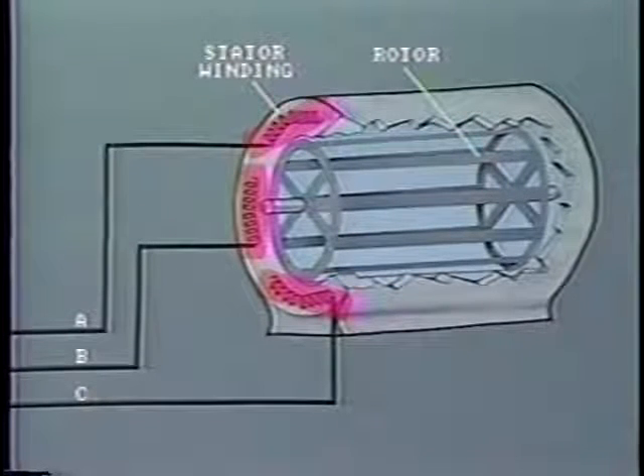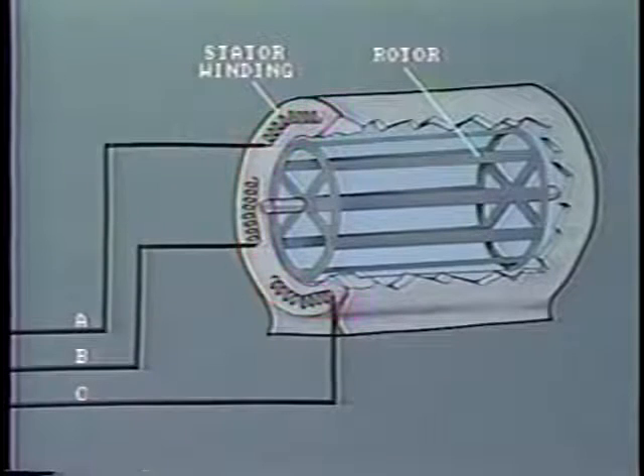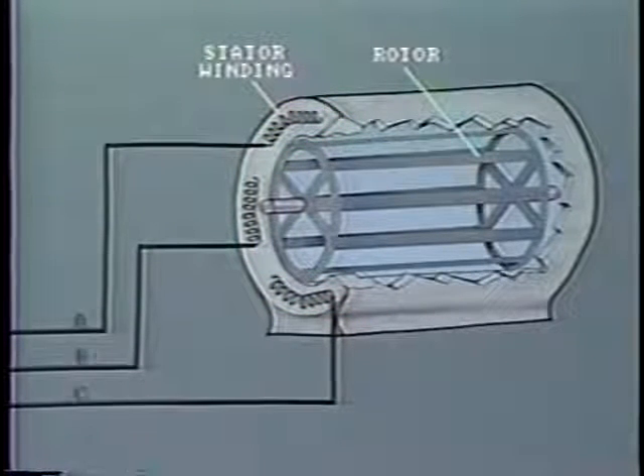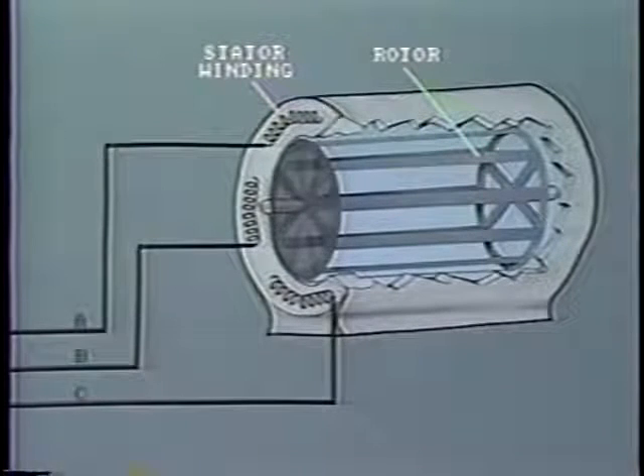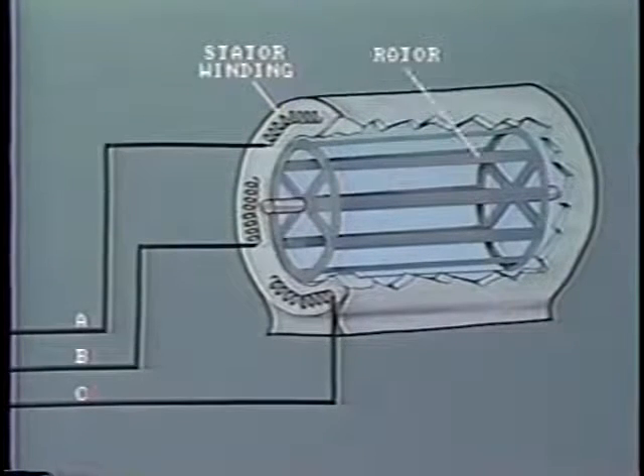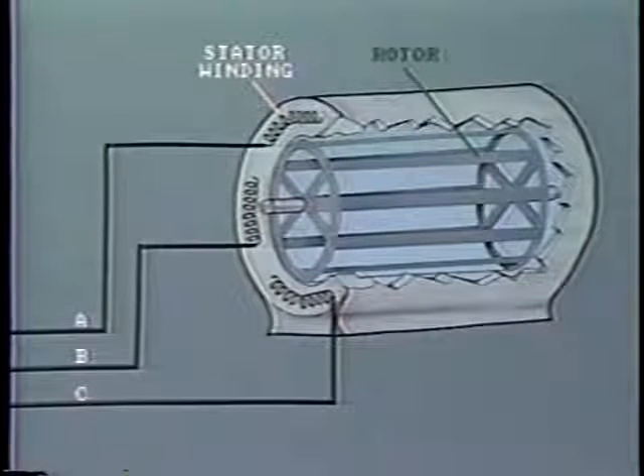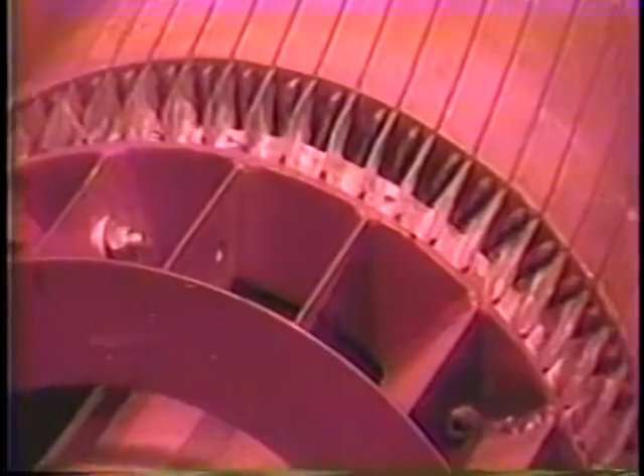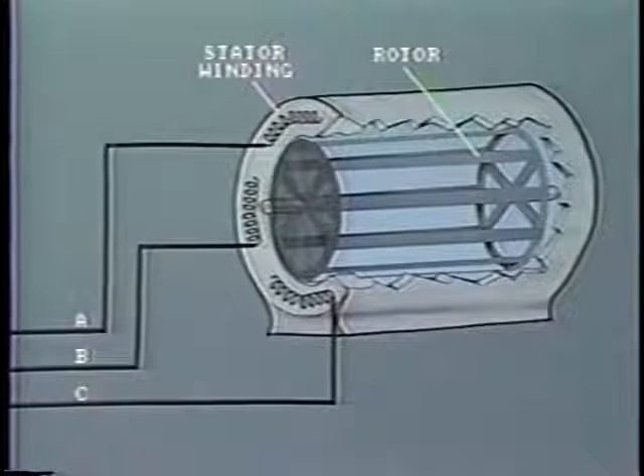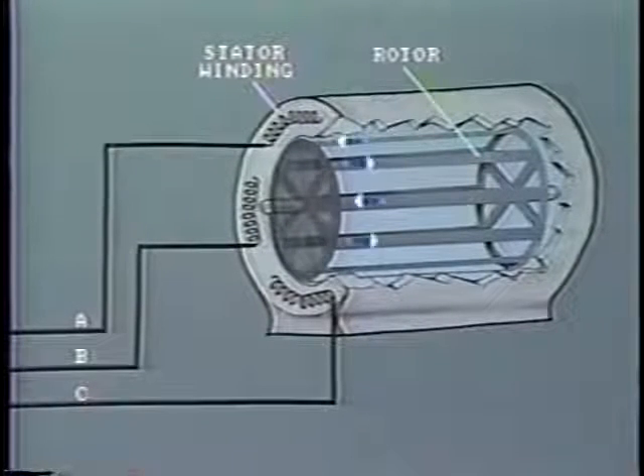The stator windings are placed around the stator iron core in such a manner that when a three-phase voltage is applied, a rotating magnetic field is set up around the rotor. Usually, the rotor is nothing more than a series of solid conductor bars short-circuited at each end to form what looks like a squirrel cage. You know the type when the squirrel or mouse runs to spin the cage. In order to improve the magnetic circuit, the conductors are embedded in a laminated iron core. The flux of the rotating magnetic field cuts the rotor conductors and induces a current flow as the conductors are short-circuited.